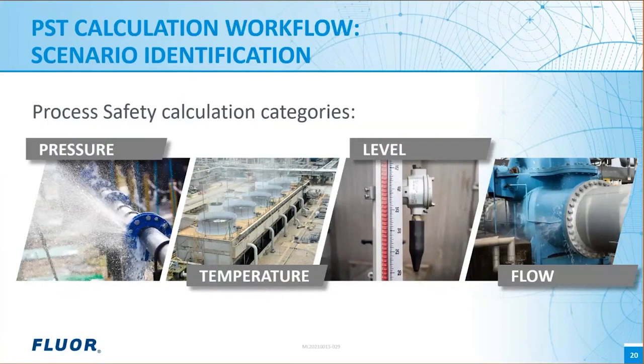So for example, in the context of pressure, there's debate amongst clients and projects about where the point of failure should be defined. So on some projects, I've seen the point of failure defined as the hydrotest pressure. On other projects, I've seen it defined as 1.1 times the system design pressure, and so on. So there are no firm rules on this, and it usually pays to agree some of these criteria upfront with your client. And FLUOR has a number of systems, such as the use of process bulletins to disseminate information to engineering teams quite quickly and efficiently, which really helps.